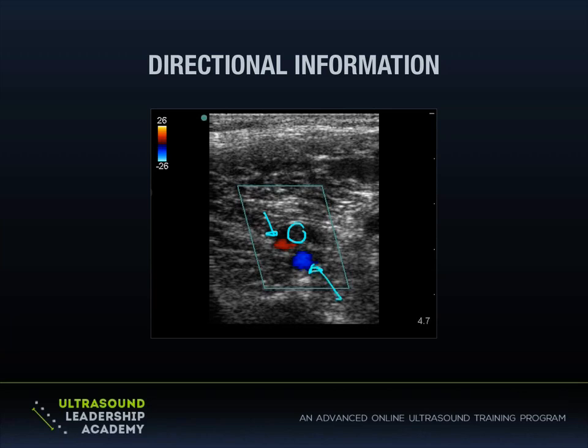And how do we know that? Well, up here is your key, and positive shifts are the ones listed up top, and negative shifts on the bottom. So in this case, flow away from the transducer is in blue, and towards the transducer is in red. And this is a typical convention. This is something called BART, or blue away, red towards. Now, this can be switched. You can invert this scale by pressing the buttons on the machine, and you could put blue on top and red on the bottom. But by convention, blue is away, red is towards, and that's what we're seeing in this case.